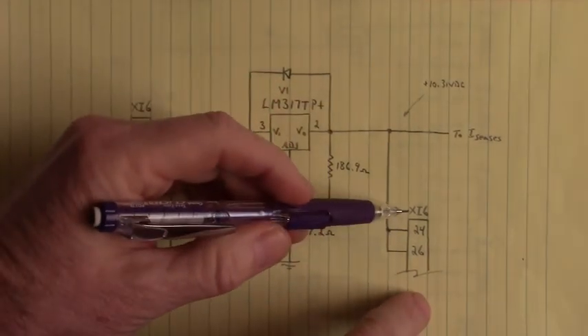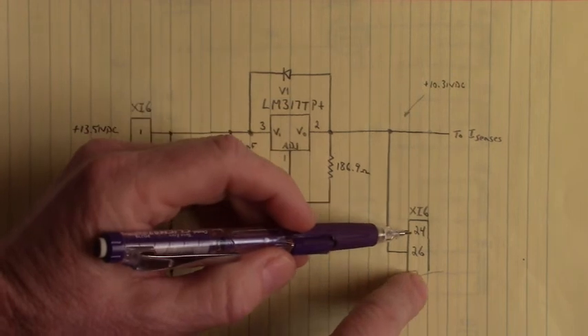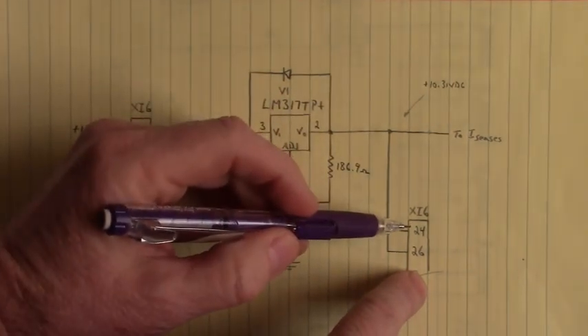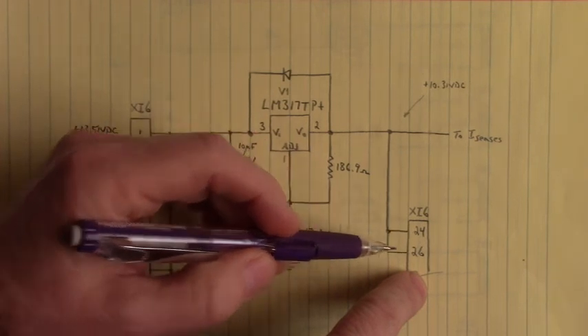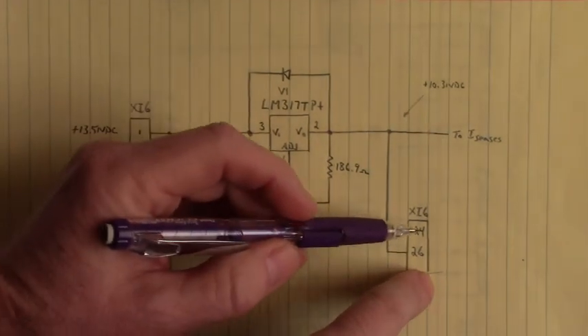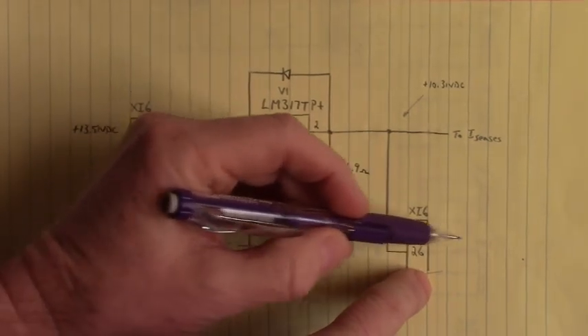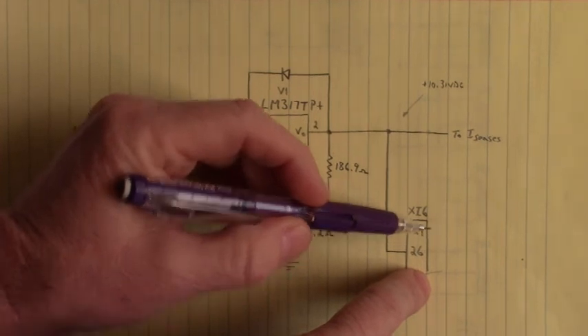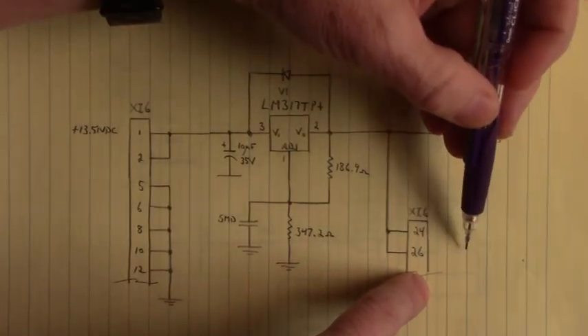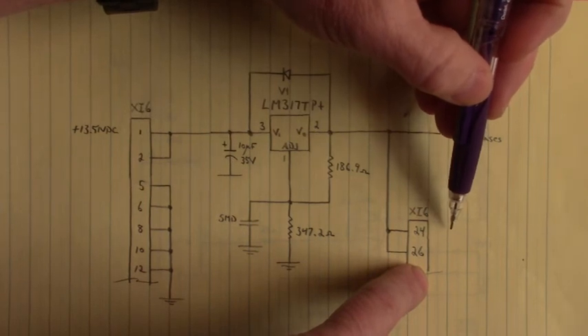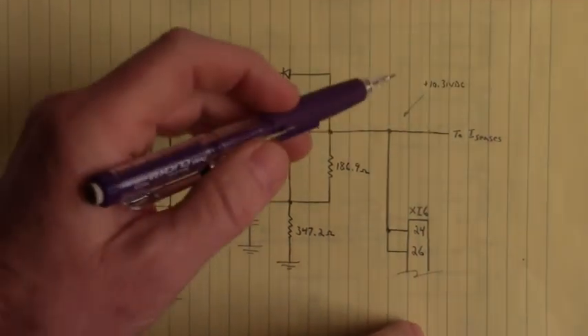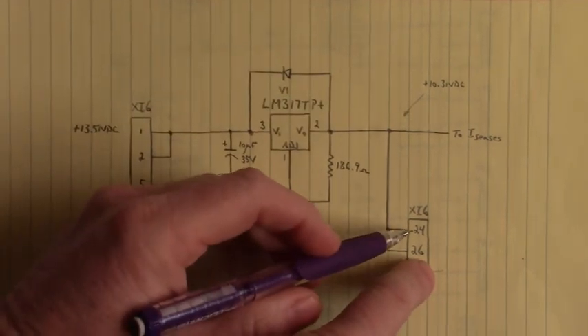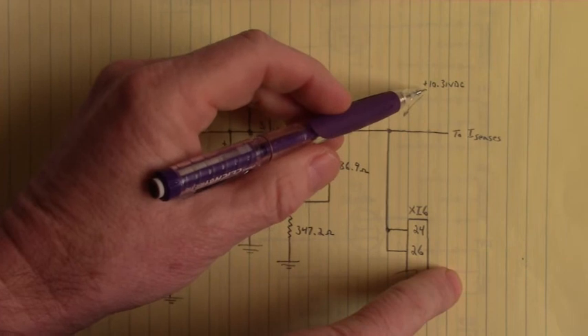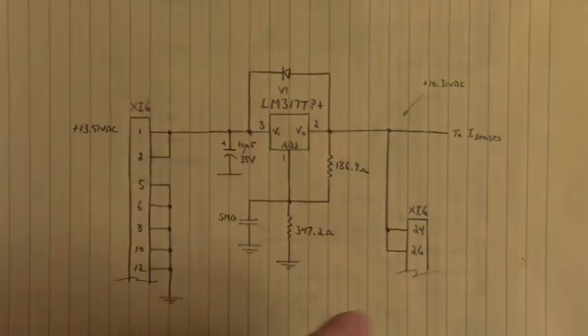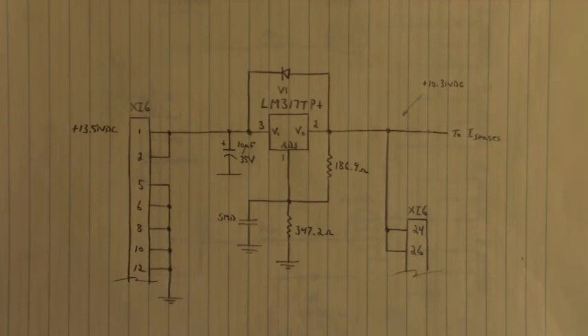Now, if you look down here on that same ribbon cable XI6, this 10 volts runs up into the control board on pins 24 and 26. And y'all can work this out too if you want to. I just don't have time to do that. But I am guessing that this input to the control board, you'll find a monitoring circuit that's looking at that 10 volts. And that monitoring circuit, when it doesn't see that 10 volts to the current sense modules, says, hey, we got a problem. We better spit up Alarm 71 and shut the drive down.